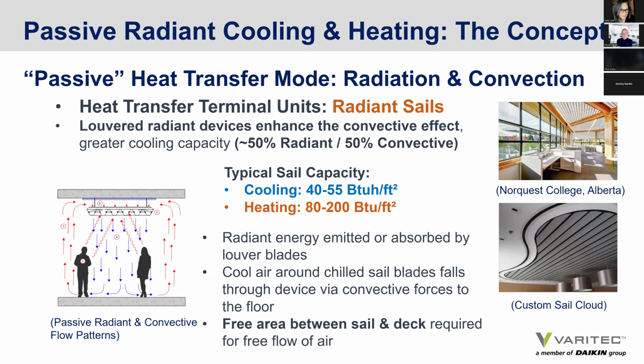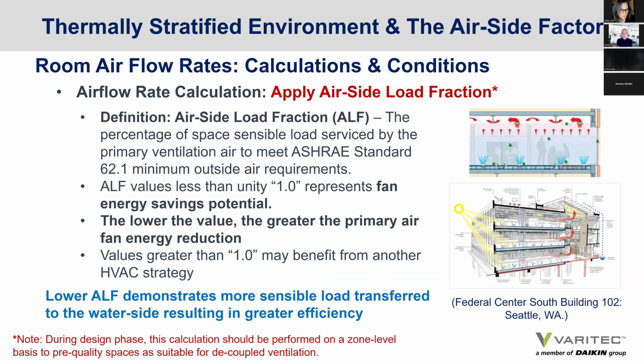Now, when you're designing to a radiant system, an engineer needs to pay attention to what is called the airside load fraction rate. So how do you design a radiant system? And that includes even for underfloor air systems. What you do is you define the minimum outside air requirements per each zone per ASHRAE Standard 62.1.